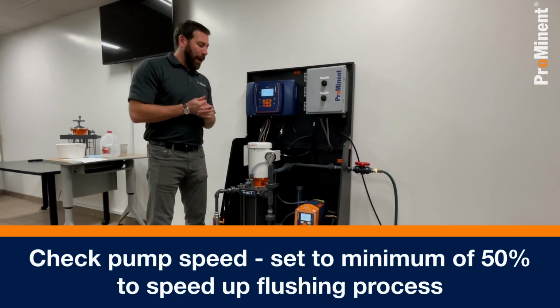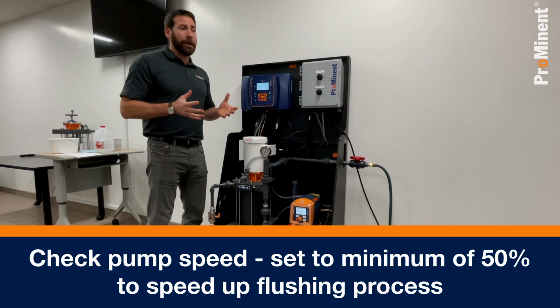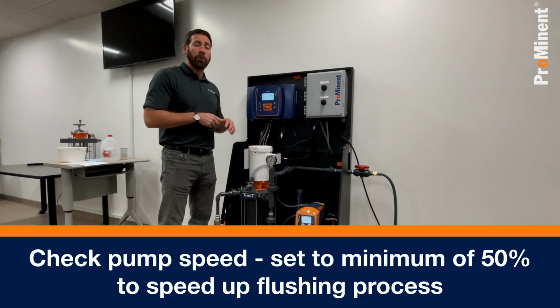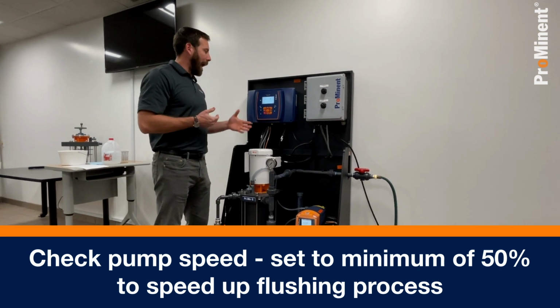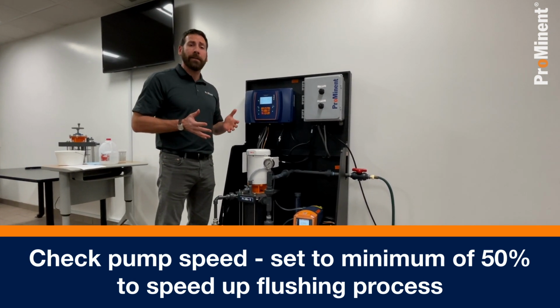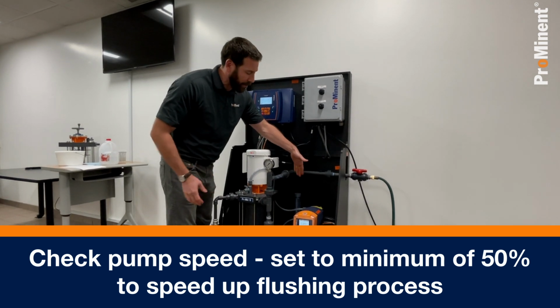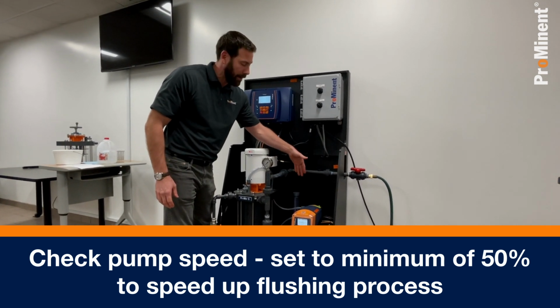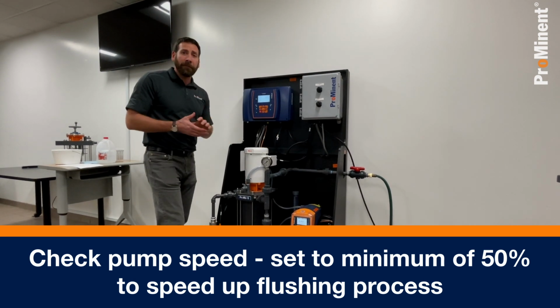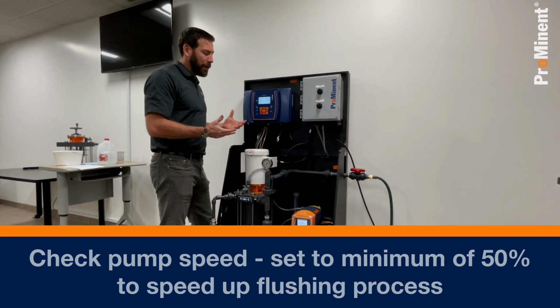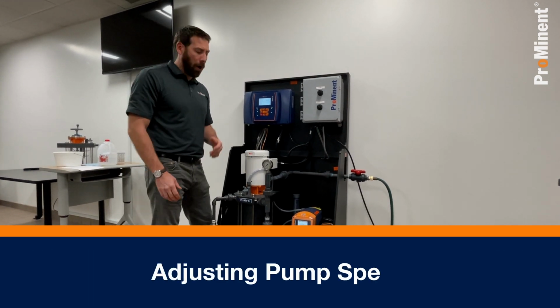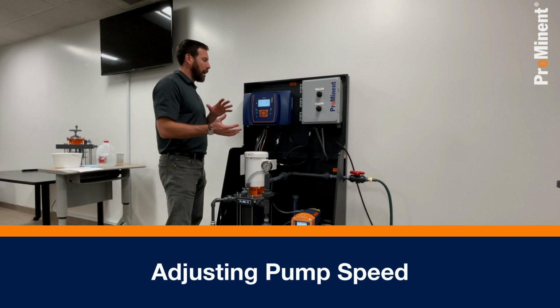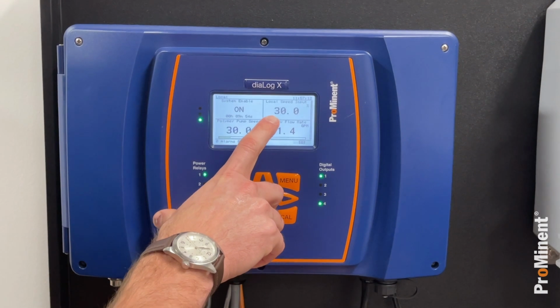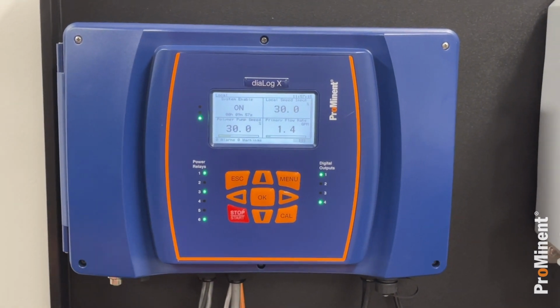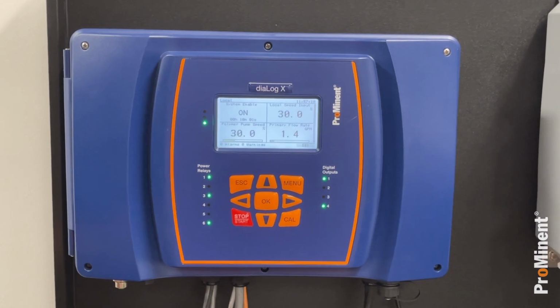After I have that filled up, I may want to look at my pump speed. I would recommend that you set your pump speed in the controller to a minimum of 50%. So right now, our unit's currently running at only 30%. So it would take a long time for it to actually pull down all that mineral oil out of my calibration column, which is fine if I want to wait around and allow it to do that. I'm going to speed mine up just so I don't have to wait so long for it to pull it all out of there. So in order to do that, I want you to come up here to the controller with me and I'll walk you through the process. You can see right here our local speed is at 30%. In this case, I'm just going to put it all the way up to 100% because we have a pretty small pump on this unit.